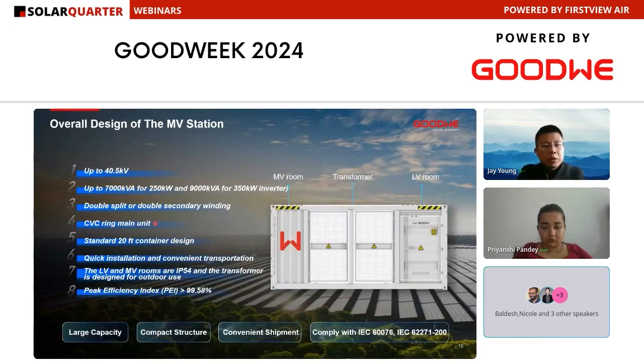Also, we have our transformer station products. It's like everything is inside the container. So the transformer is in the middle, and on the right side is the LV room, where it is connected to the inverter. And on the MV side, after the transformer steps up, it goes to 20 kilovolts or 36 kilovolts, and the maximum is 40.5 kilovolts. And the capacity of the transformer can reach 9 megawatts for the 350 inverter. And for the MV part, we can provide an RMU, ring main unit.